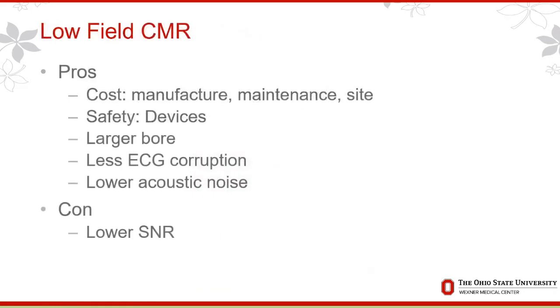Low-field CMR demonstrated improvements, specifically with lower cost to manufacture and maintain the scanner and lower cost of site production. With low-field CMR, there is less device heating, a larger bore to reduce claustrophobia and increase safety for larger patients, less ECG corruption, and lower acoustic noise. One obvious con inherent to low field is lower signal-to-noise ratio. However, with advanced acquisition, reconstruction, and image processing methods, this has truly changed and leveled the playing field with respect to SNR.